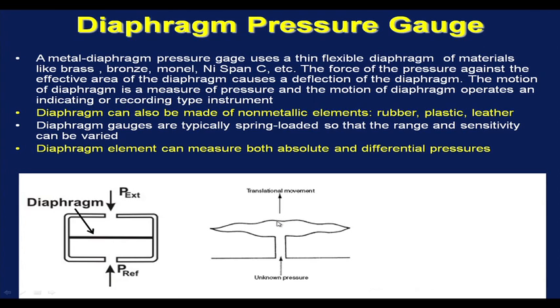This movement of the diaphragm can be used to move a pointer and scale mechanism. So, the deflection can be read, and that will be taken as a direct measure of the pressure being applied. Diaphragm can also be made of non-metallic elements such as rubber, plastic, leather, etc.